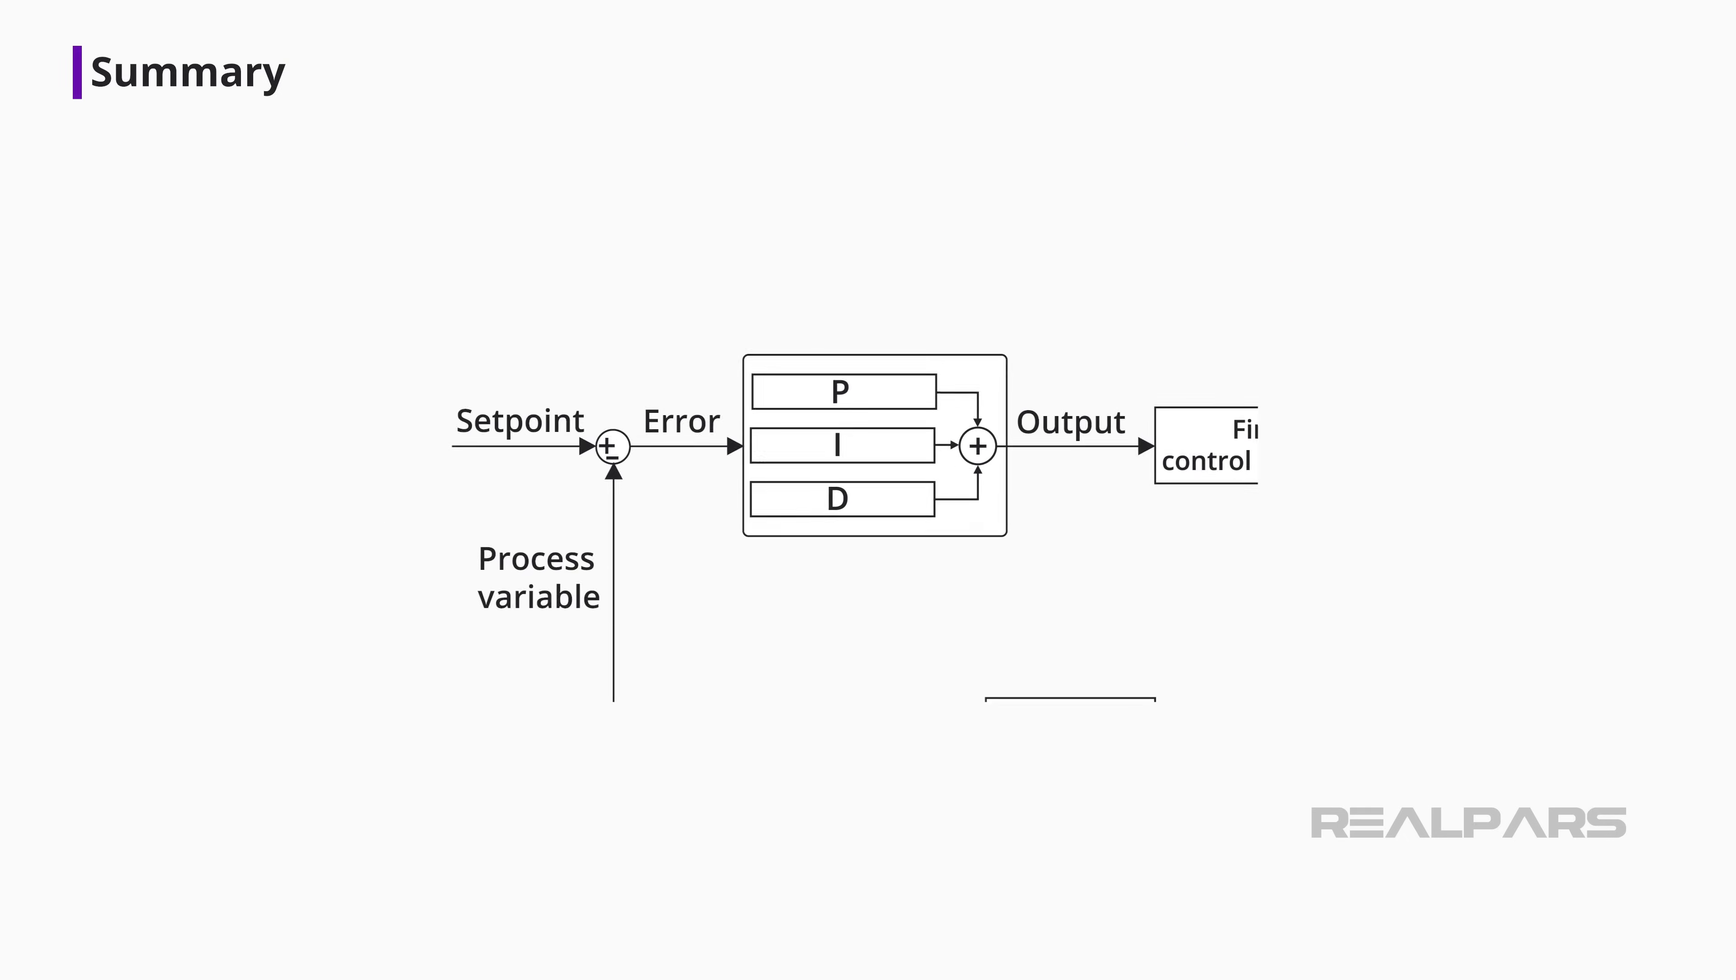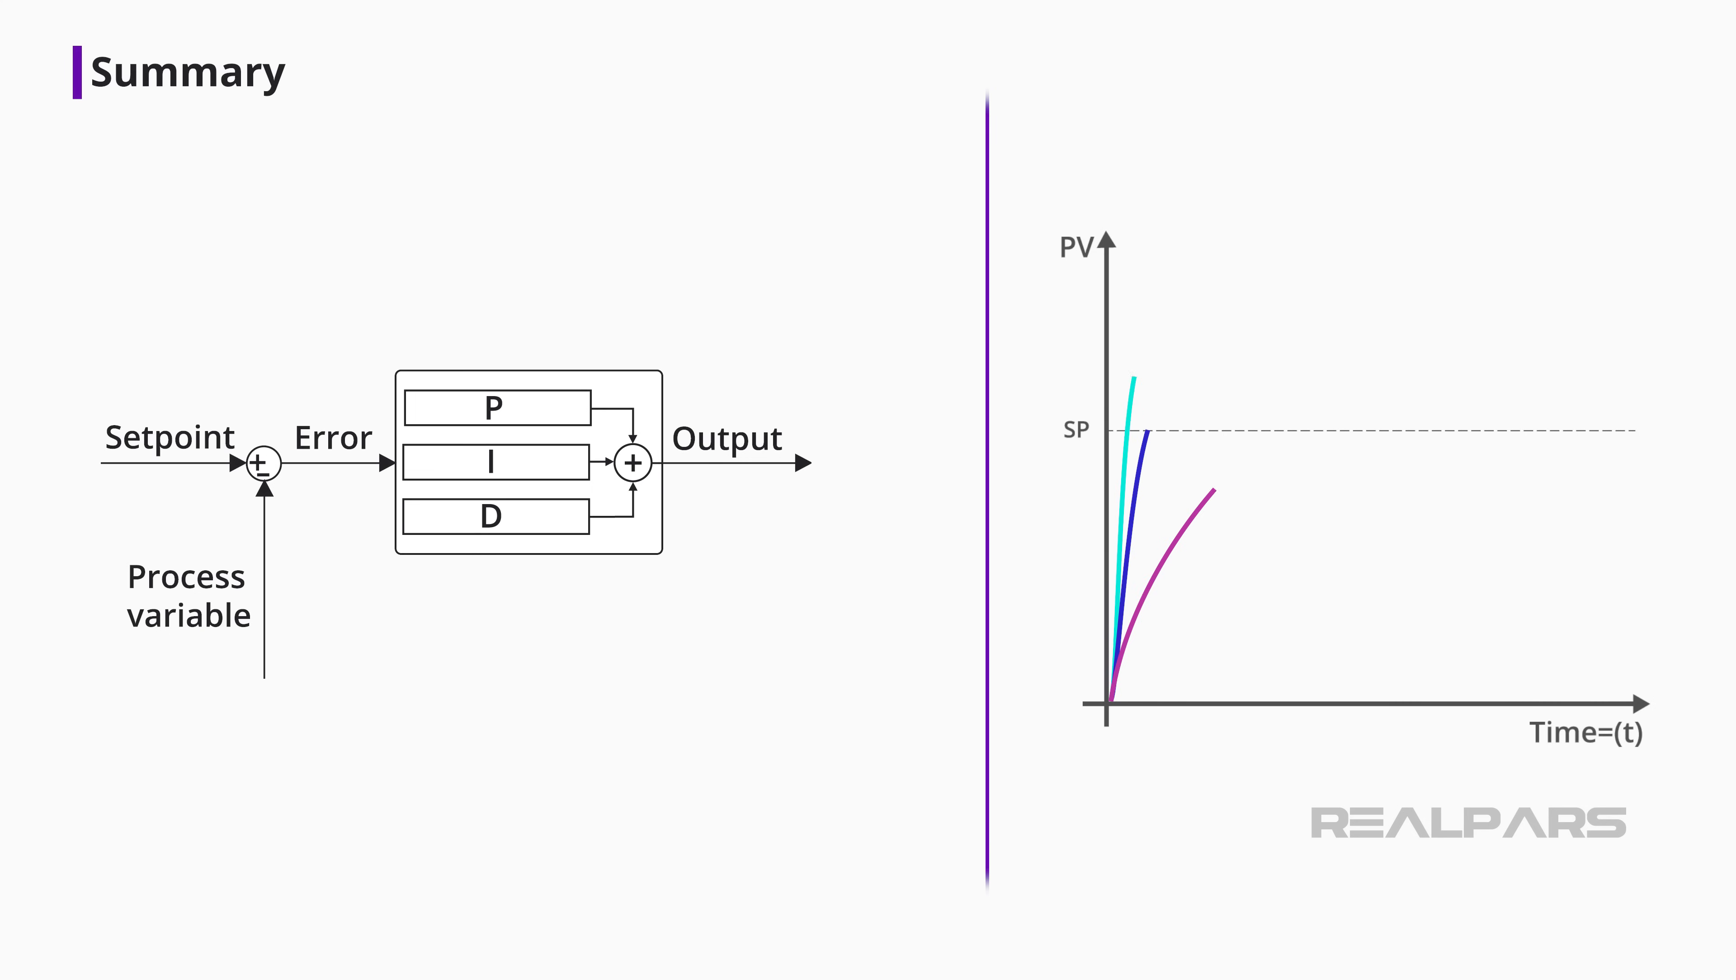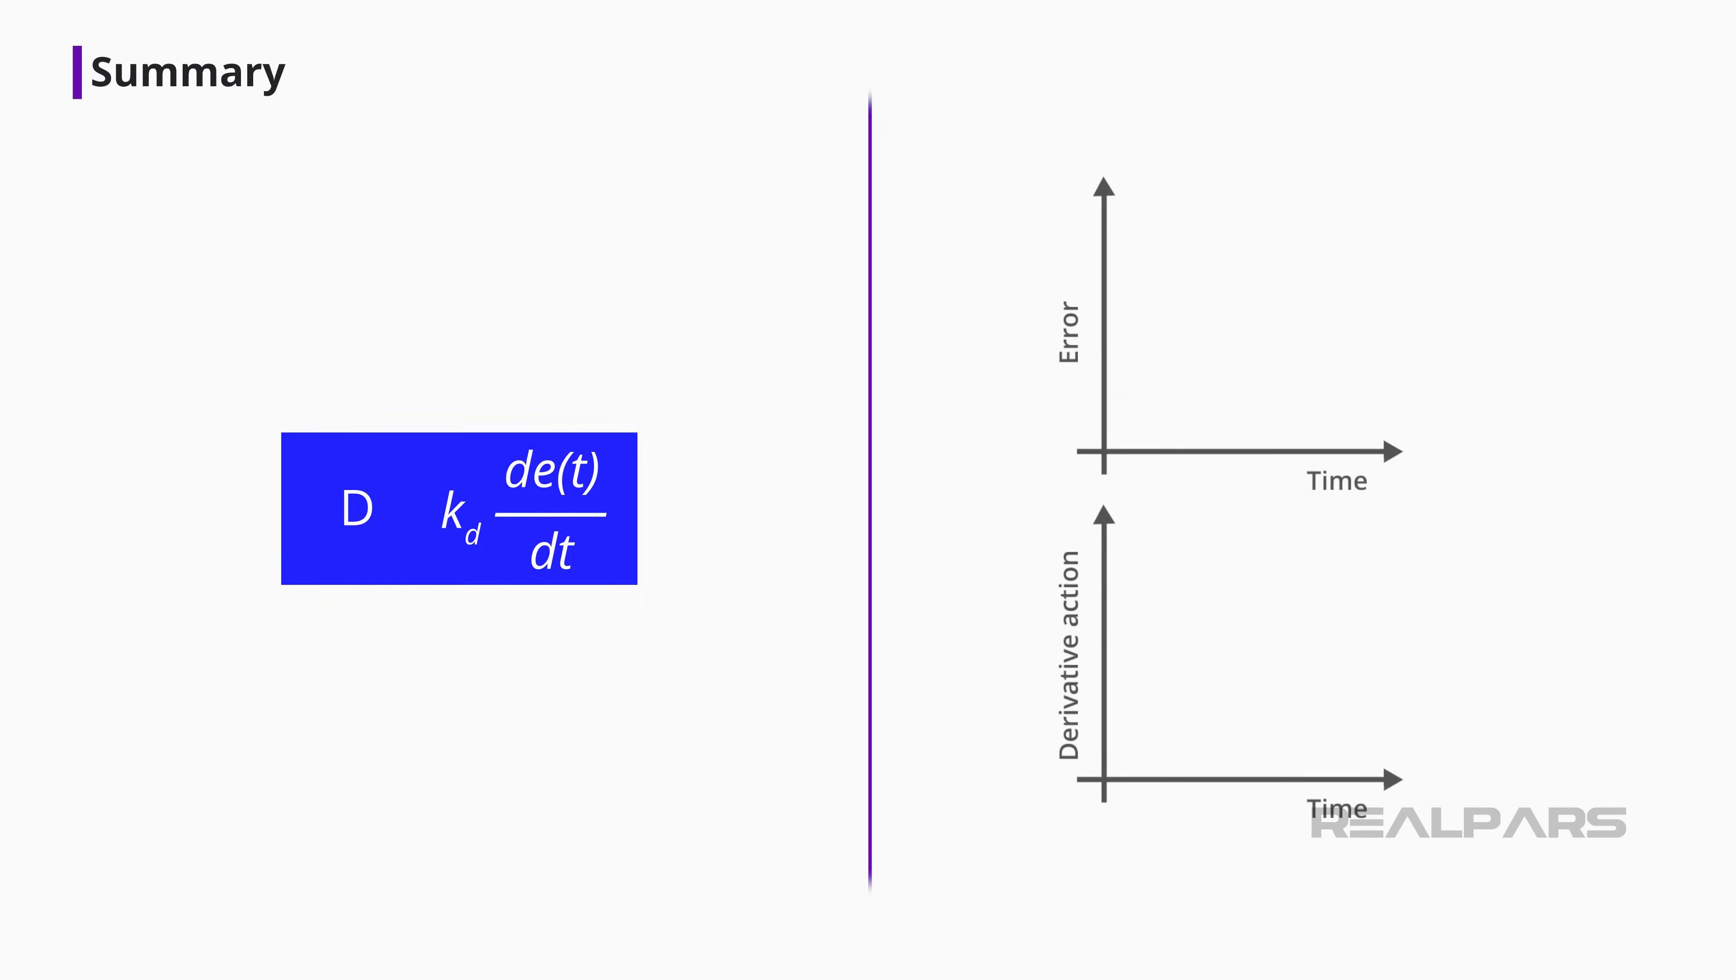The PID controller determines how much and how quickly correction is applied by using varying amounts of P, I, and D action. The Proportional block creates an output signal proportional to the magnitude of the error signal. The Integral block creates an output proportional to the duration and magnitude of the error signal. The Derivative block creates an output signal proportional to the rate of change of the error signal.